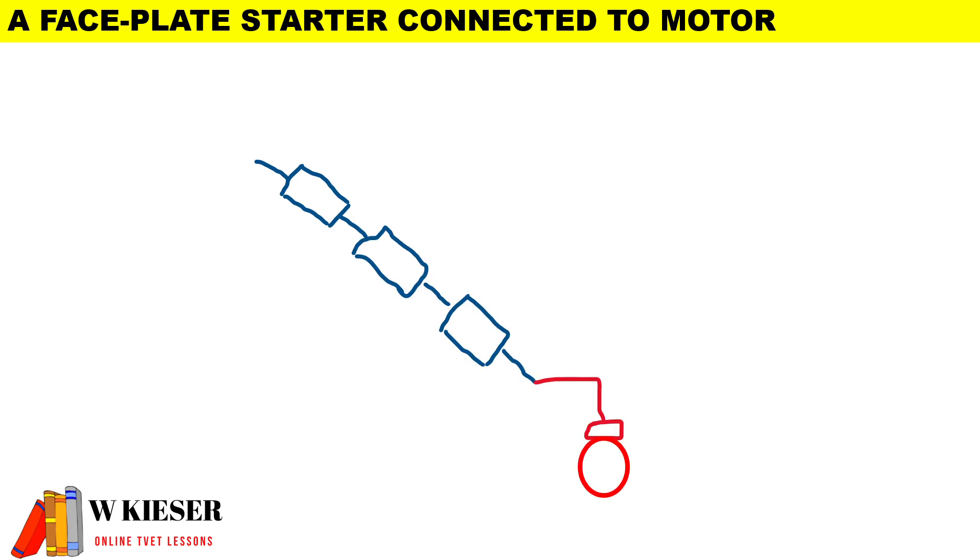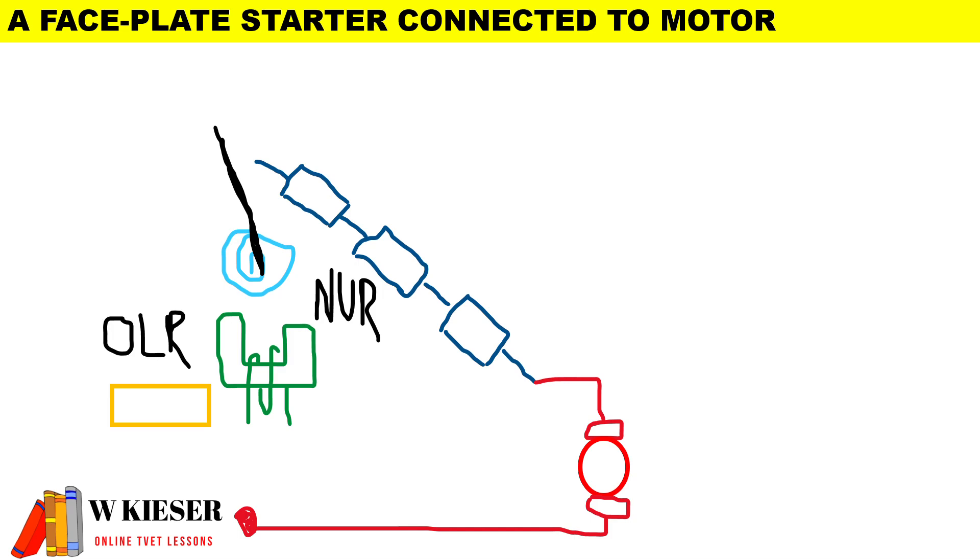For our faceplate starter, we put resistors in series with the armature to limit current at start. We have a position arm which moves from the off position to stud one during start, and we have two protective devices: the overload relay and the no-volt relay.